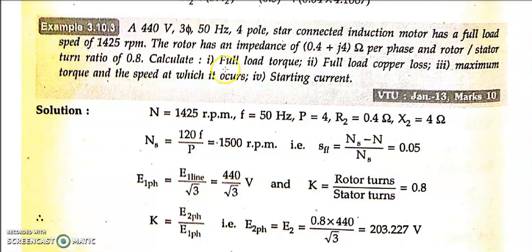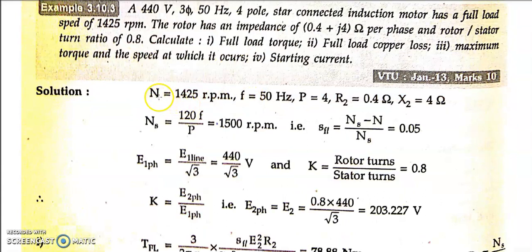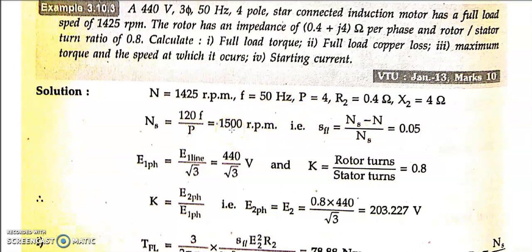Let us begin. First, write the data: full load speed n = 1425 rpm, f = 50 Hz, p = 4, r2 = 0.4 ohm, x2 = 4 ohm. Calculate synchronous speed: ns = 120f/p = 120×50/4 = 1500 rpm. Now calculate full load slip: sfl = (ns − n)/ns = (1500 − 1425)/1500 = 0.05.